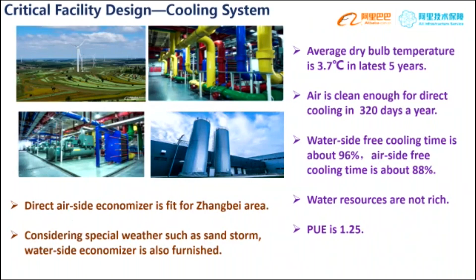Direct airside free cooling time is about 88%. But in Zhangbei, water resources are not rich, so we adopt direct airside economizer in our cooling solution, and considering special weather such as sandstorms, water side economizer is also furnished. Finally, we got power usage efficiency of 1.25.